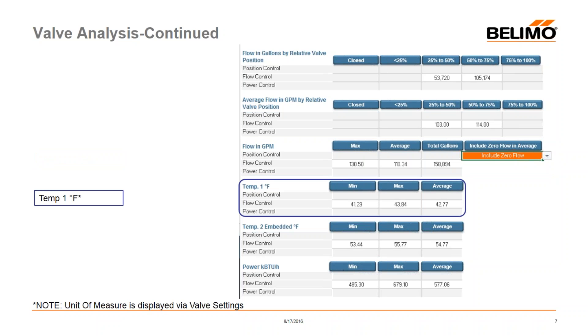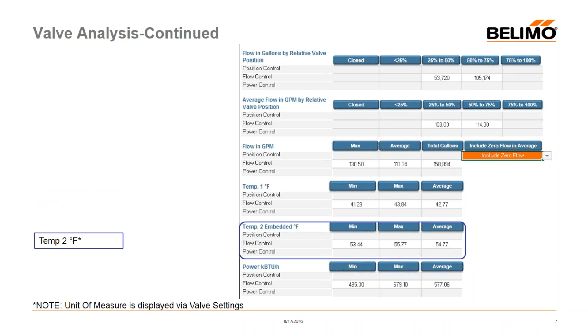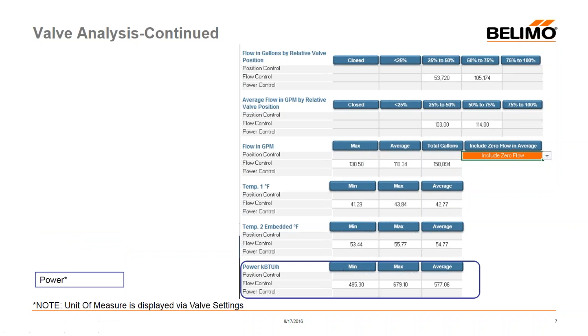The temperature boxes show T1 and T2 — either supply or return depending on valve installation — displaying minimum, maximum, and average temperatures. In this example we're averaging about a 12-degree delta T across the board, which is pretty good. Units of measure are displayed per the valve settings on the dashboard, so if set to Celsius it would say degrees C. The power box then shows minimum, maximum, and average power or BTU output of that coil.